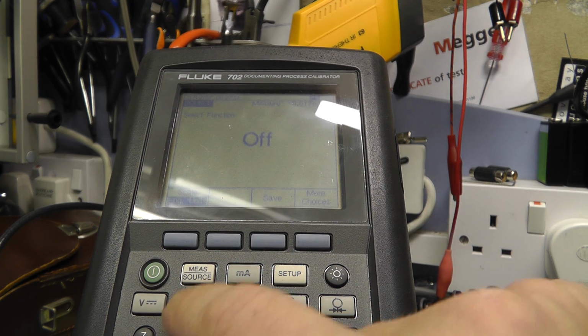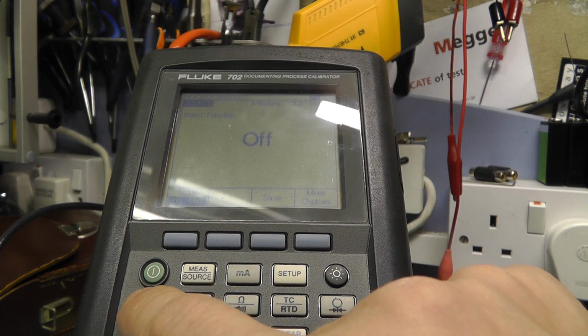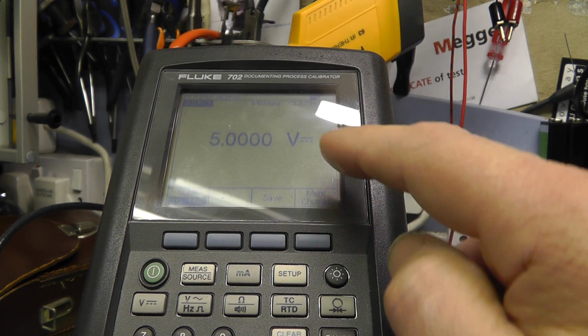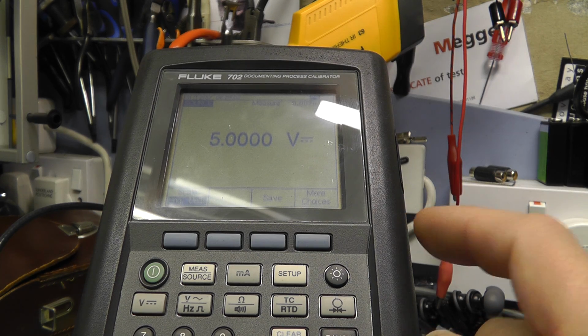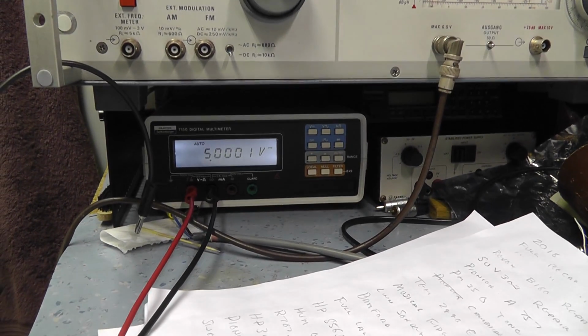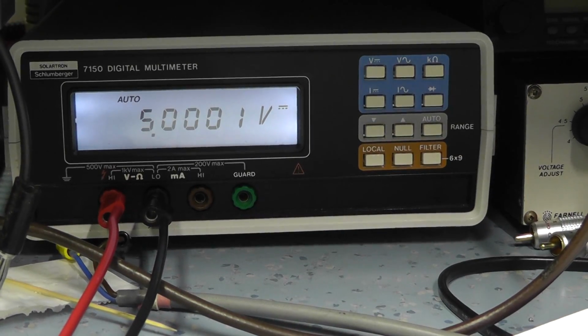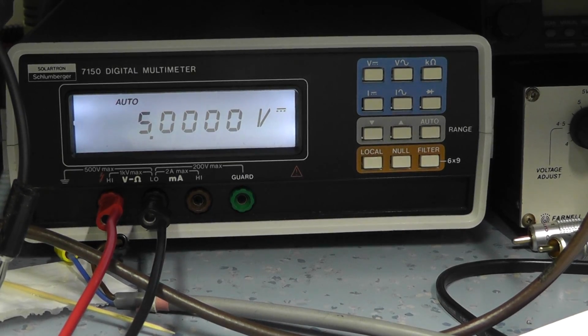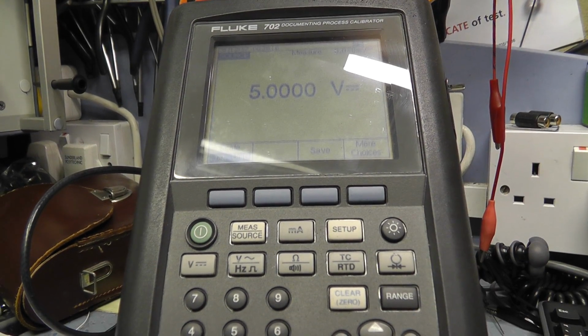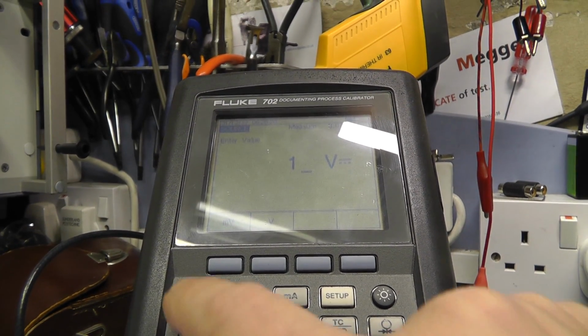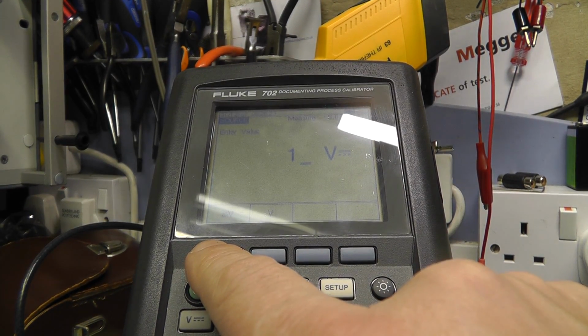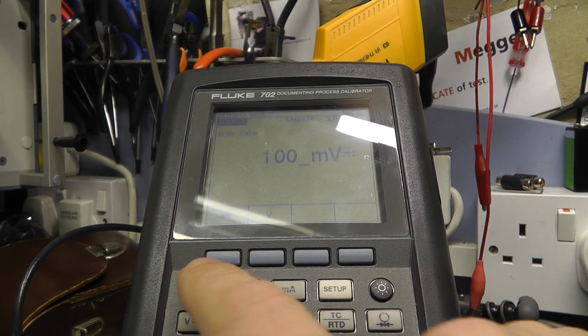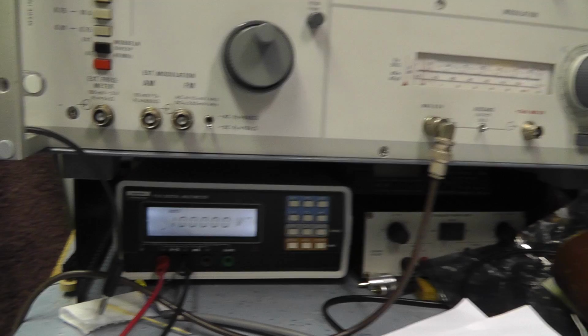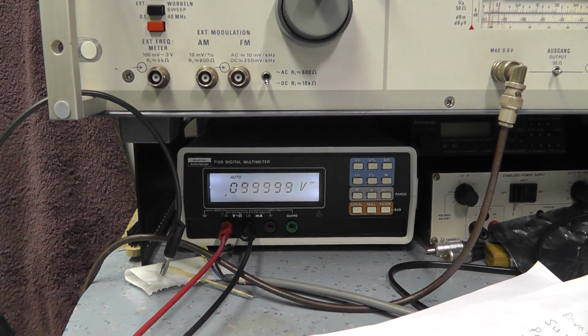It's right in a minute. Then I enter 5 volts. So at the moment the unit is sourcing 5 volts, and if you turn around and have a look at the Solartron, it agrees that it's 5.0001 volts, so that seems to be working fine there. Let's try the lower voltage range - let's try 100, and I can select millivolts here. Obviously I can put 0.1 of a volt, that's the same. 100 millivolts, enter, and it's sourcing 100 millivolts. The Solartron clearly shows 100 millivolts, which is reassuring because obviously the meter's well calibrated. That seems to be working pretty well.